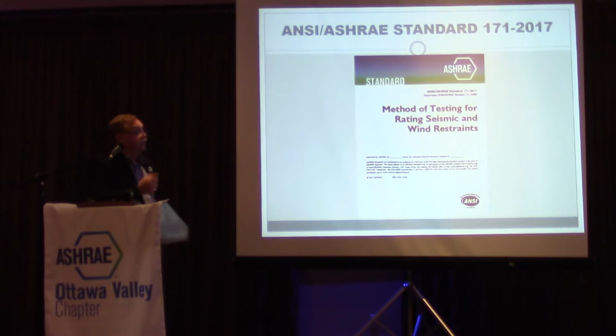ASHRAE has a method of test for seismic restraints, a method of testing seismic rating and wind restraints. We keep changing the name. Basically it's a series of tests for things like these vibration seismic restraint devices. When it fails, that's it. So these undergo testing and you come out with a rating, saying this is good for 1,000 pounds horizontally, 900 pounds vertically, whatever the number happens to be.